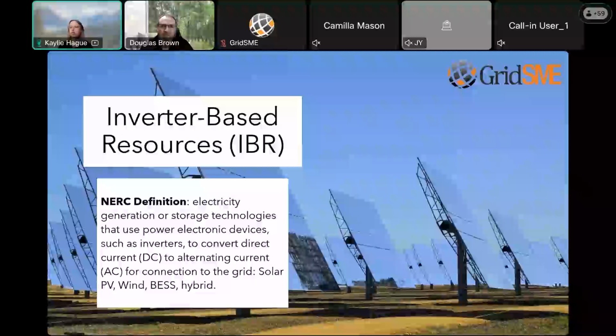So this will be your solar PV, wind, battery or BESS, and any hybrid of those. These storage systems are increasingly replacing traditional synchronous generation in the power grid. If we look at thermal or hydro generation, they're primarily based on the physical design of a generator, but the behavior of IBRs is primarily driven by power electronic controls, which provide a higher degree of flexibility, but also higher electrical complexity.